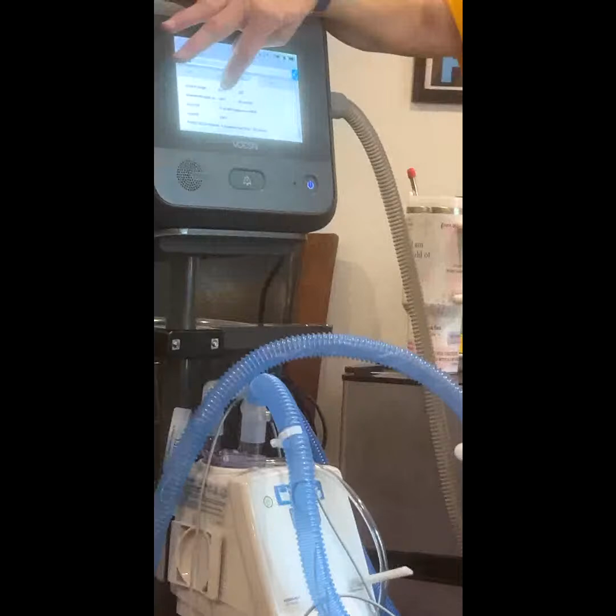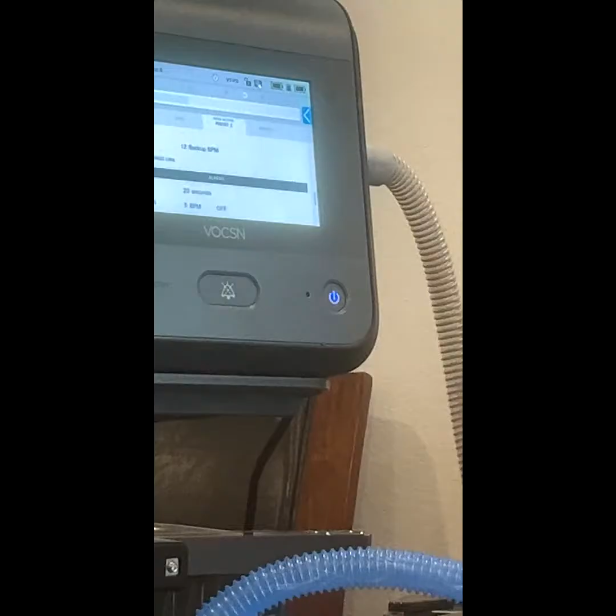Minute ventilation, breath rate high and low, inspiratory pressure high and low, PEEP low and high, circuit disconnect, high pressure alarm delays. Those are not a whole lot of alarms like Trilogy and Evos have. They have a little bit more than what anybody thinks. So, questions on any of that? No? Okay.